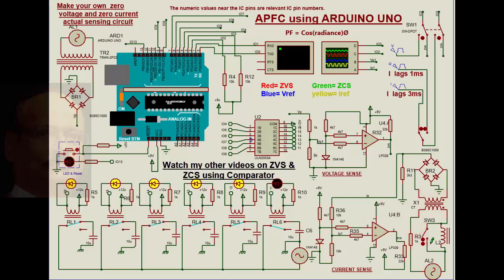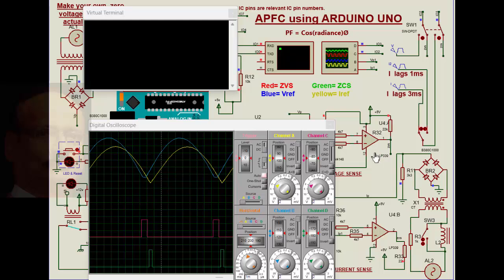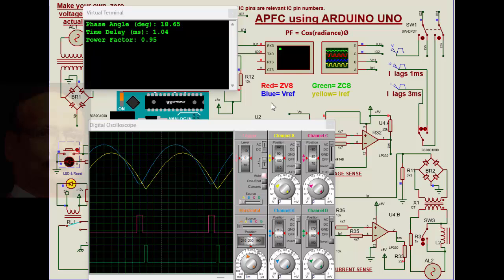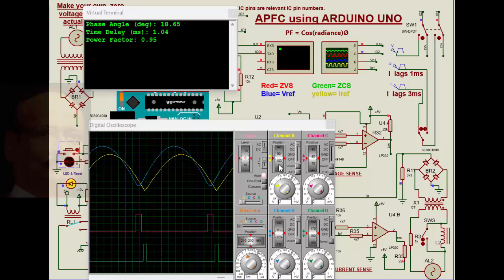We try to operate this and then reset it. The waveform shown is the actual waveform — there is a difference between voltage and current. The blue is the voltage reference and the yellow is the current reference. You can see there is a time lag, and it is trying to correct the power factor — it has already corrected it. The relay is operating, but the capacitor is not doing any work, as this is as far as the inductive load is concerned.